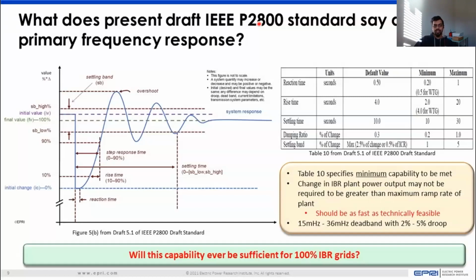So primary frequency response as we know it today, the draft P2800 standard speaks about this primary frequency control in the following manner: supposing you have a change in the system quantity, let's say a step response kind of a change, and you have a change in the system quantity being, let's say, frequency here, then the minimum expectation from an inverter-based resource is that its response will follow a trajectory which is governed by these minimum values. So it will have a minimum reaction time of 0.2 seconds, a minimum rise time of 2 seconds, and a minimum settling time of 10 seconds, with a minimum value of damping ratio and settling band.